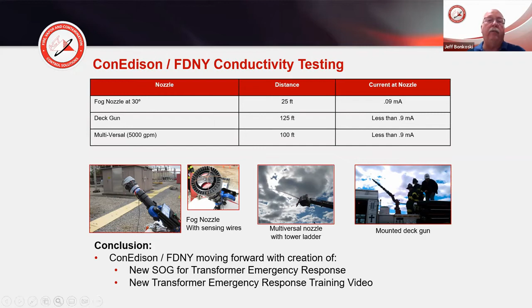And then it shows a Multiversal 5,000 GPM nozzle at 100 feet. So they tested all of these different nozzles at all of these different distances, and they came up with their SOGs for how to deal with these transformer fires using F500. I mentioned early on, it's a Class B fire in a Class C environment. So they're able to deal with these transformer fires so that they don't have a huge impact and don't have a citywide blackout.